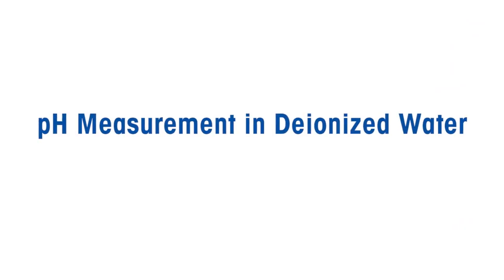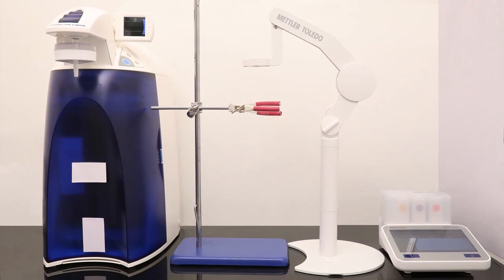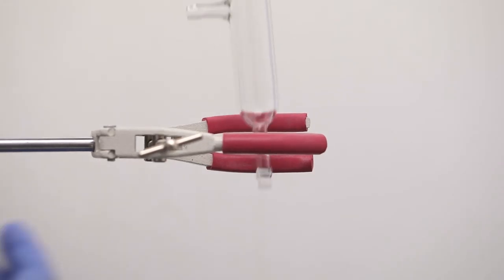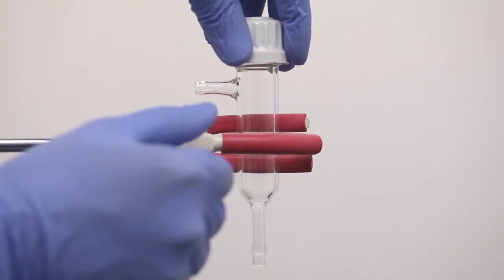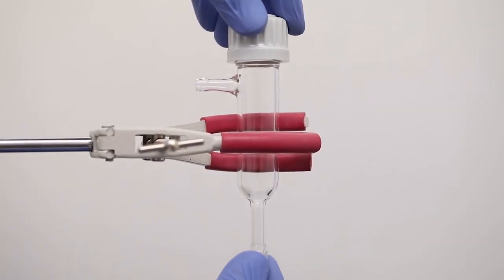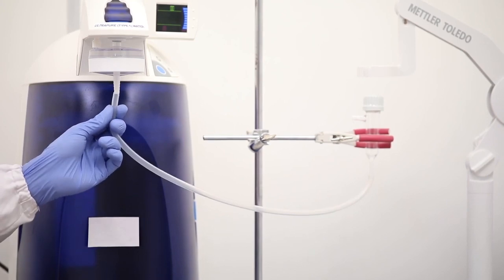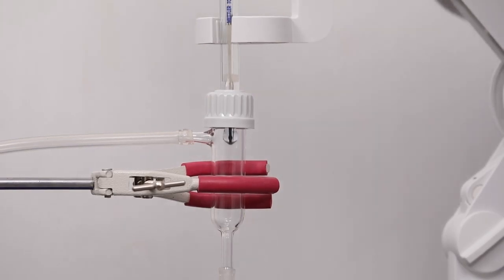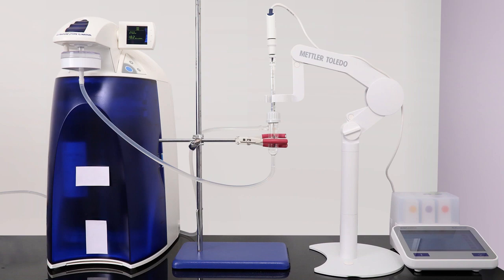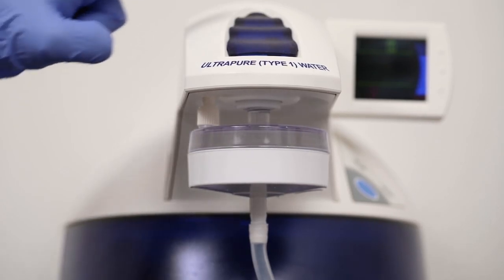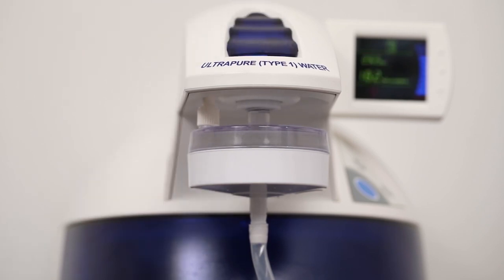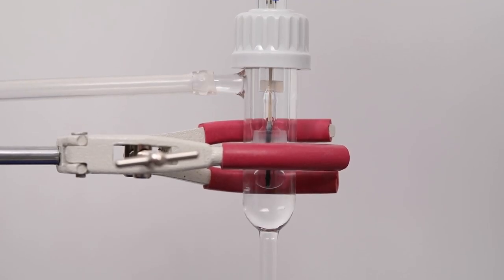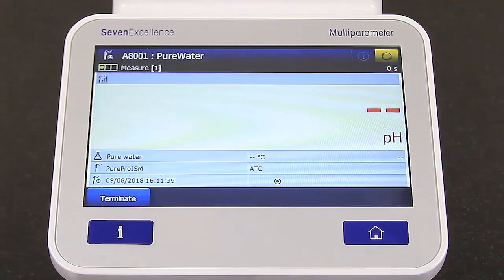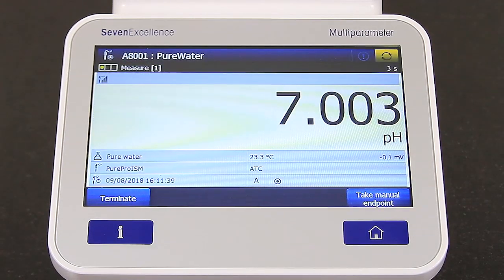As explained before, pure water samples are vulnerable to absorption of atmospheric carbon dioxide. Low ionic water samples with conductivity less than 100 microsiemens per centimeter should be ideally measured in a closed system, protected from ingress of air. If we have a direct source of purified water, it is recommended to use a flow cell as it helps to maintain the sample integrity. In case of water samples which are supplied in containers and do not have a direct source, it is recommended to degas the sample before the measurement.